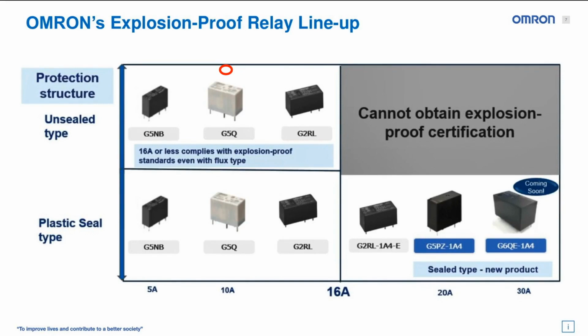So we offer both sealed and unsealed types of these products, all with explosion-proof ratings. Once we get past the 16 amp marker, we're now looking into that untapped territory I was mentioning. So one of the existing platform products can reach 16 amps and above. So that is one of the options for above 16 amps. We also have a newly released G5PZ, which I will talk about in a few slides. This is a sealed product for 20 amp switching. And then coming soon, in the next year, we will be releasing a G6QE sealed version. So this is a 30 amp and 36 amp product that can reach even higher loads for compressors and motors in various applications that need this sealed explosion-proof rating.